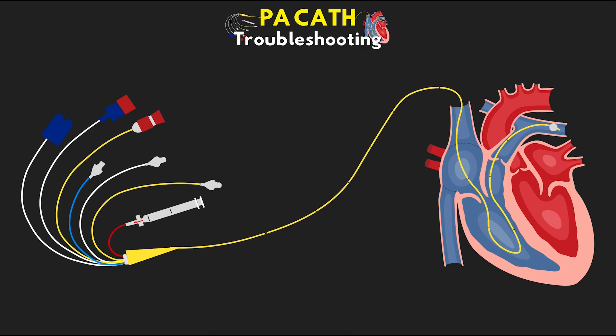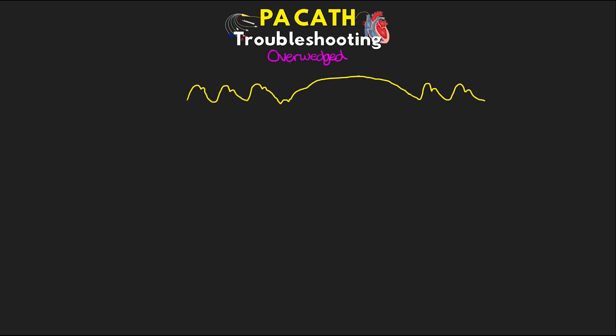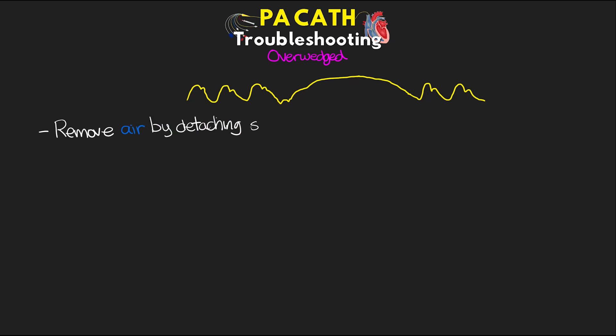Without further ado, let's dive right in. The first troubleshooting scenario is if we are over-wedged. I did discuss this in the lesson on abnormal waveforms, but I want to go over it again here so it's all consolidated. The first thing we need to do is remove air by detaching the syringe and then seeing the over-wedge waveform go back to a normal pulmonary artery waveform.